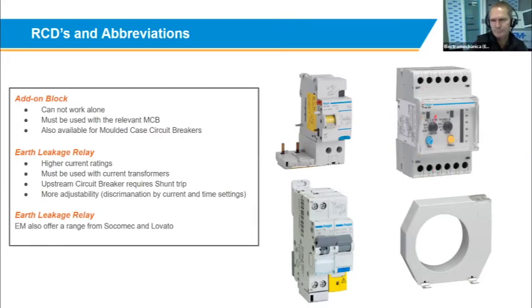So the direct connect earth leakage like these ones, where the current actually goes through it and it breaks the current. This is done through the CT. It picks up the imbalance. This unit picks up the imbalance and then sends a signal to your moulded case circuit breaker, or miniature circuit breaker, or ACB even, to trip the upstream device. The other nice feature of a unit like this is you can do discrimination in your system on earth leakage protection.